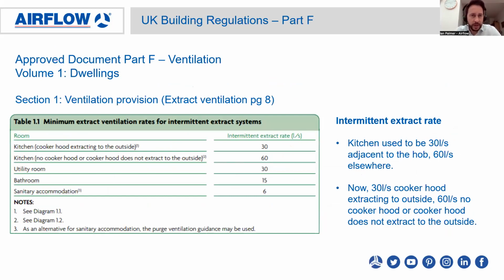So staying with part F, in section 1, there is one of the first relevant tables when you're sizing mechanical ventilation for your dwelling. So this table 1.1 lists the minimum extract ventilation rates for intermittent extract fans or extract systems. Some slight changes here to the old regulations. The kitchens used to be 30 litres a second when they were adjacent to the hob, and 60 litres a second elsewhere. And now they show 30 litres a second when a cooker hood is extracting to outside, and 60 litres a second when there's no cooker hood or the cooker hood does not extract to the outside, so where it may be a recirculating hood.